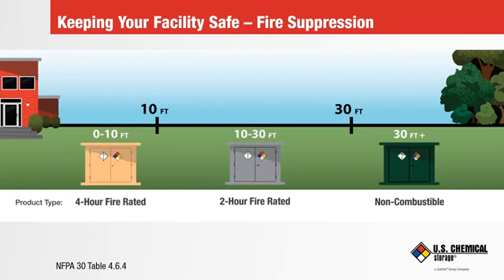Codes written by NFPA, OSHA, and the International Fire Code are all very similar but not exactly alike on setting distances. For example, most codes require the building to be 4-hour fire rated when within about 10 feet of another building. But adding a sprinkler fire suppression system will reduce the fire rating to 2 hours. At the other extreme, a hazmat building more than 30 feet from buildings, roads, and property lines does not have to be fire rated or protected by a fire suppression system.